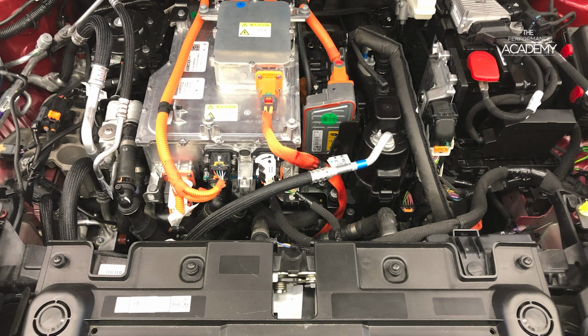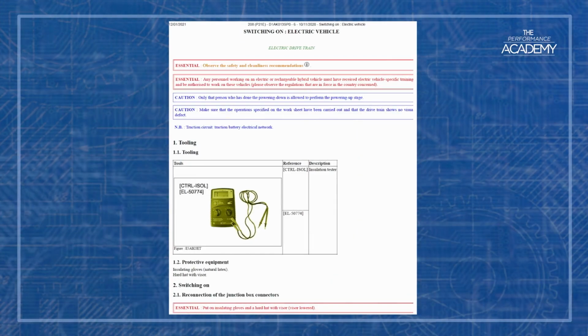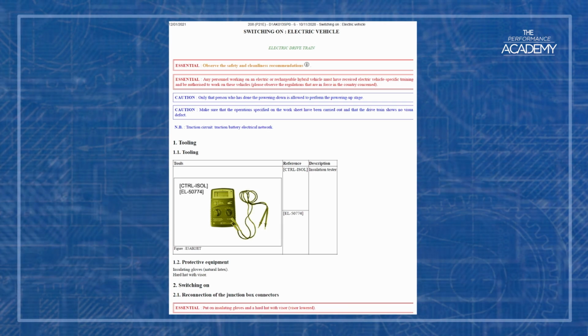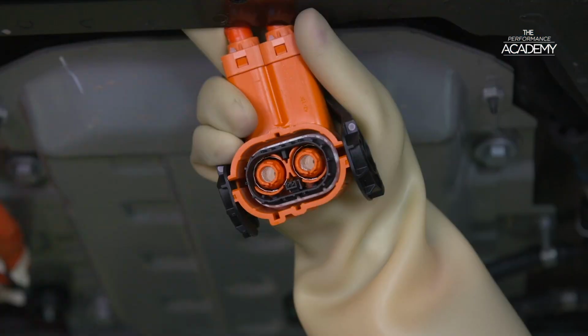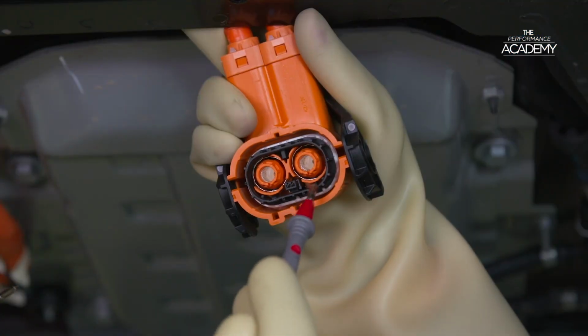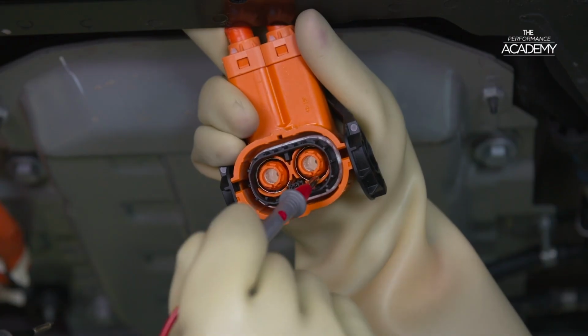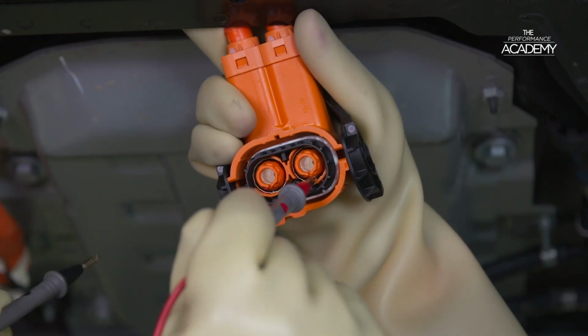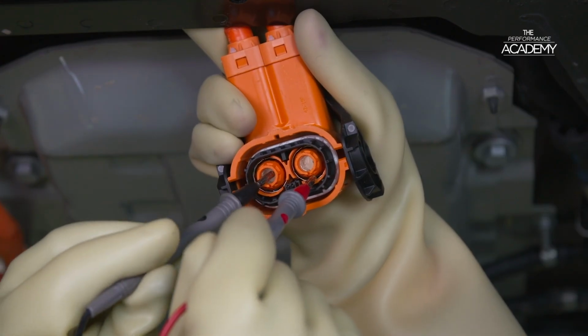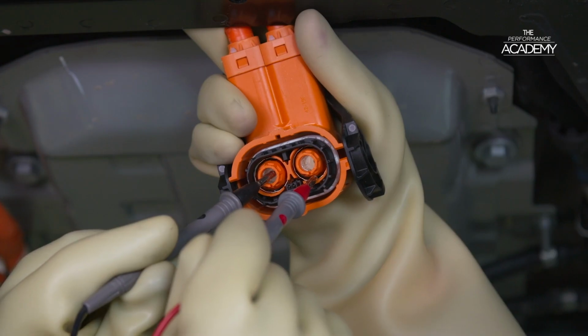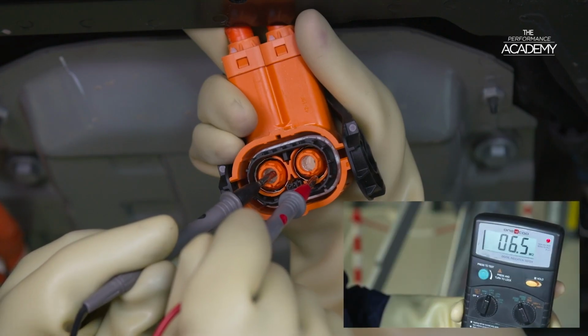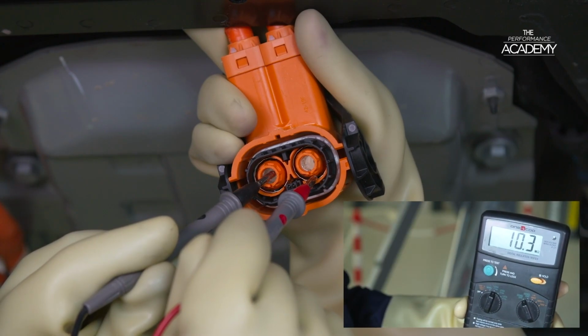The vehicle is already powered down and made safe, and we've already checked the insulation tester's functions. Following the instructions in service box, it tells us to put the negative probe on the earth at E of the electrical power circuit connector. This is the earth shield or screen which is wrapped around the insulated high voltage supply wires. Put the positive probe on the pin at D of the electrical power circuit connector, and this is one of the main high voltage supply pins.